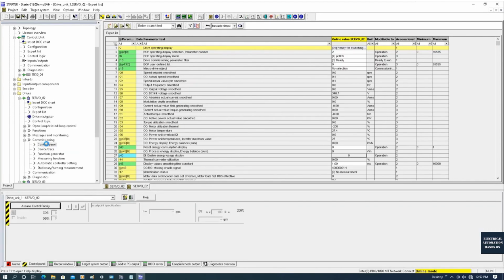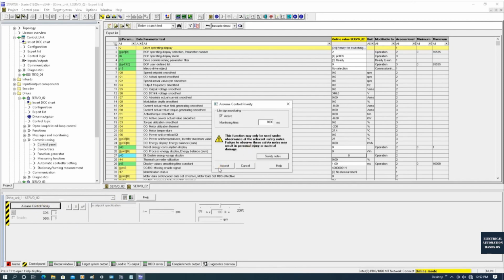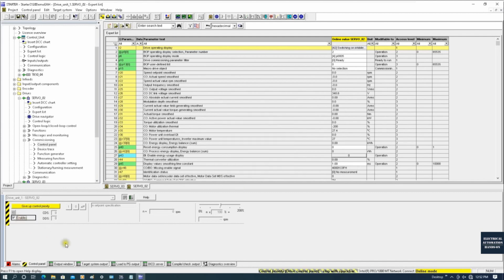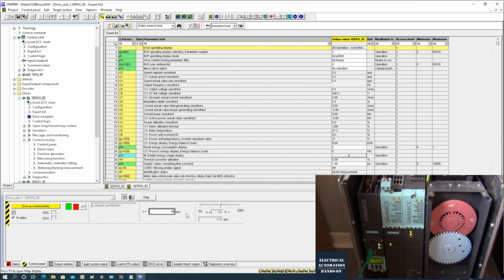Okay, double click this control panel. And make sure we are selecting the Servo 2. And then we can click this assume control priority. And once we click this, we have full control priority for this motor. And let's power on the infeed module, drive on, so we can hear this noise. And now if I set an RPM parameter, let's say 10 RPM, we can see the motor is running there. If I set 0, the motor will stop.